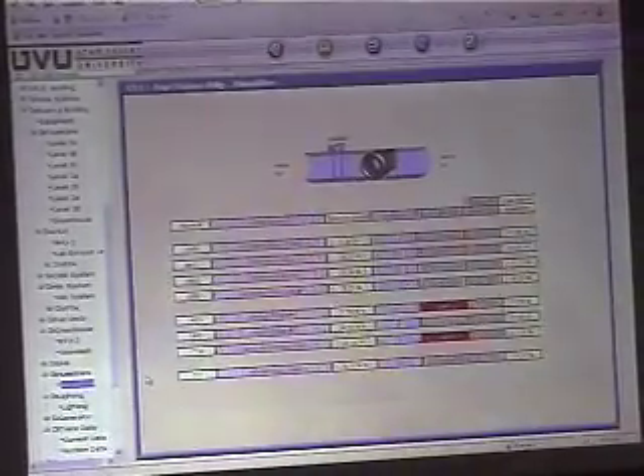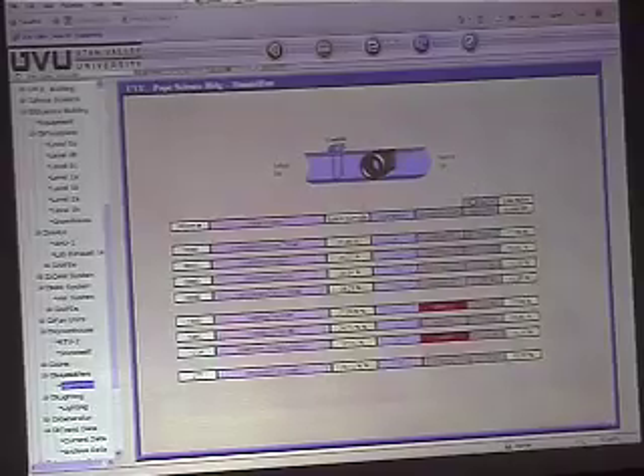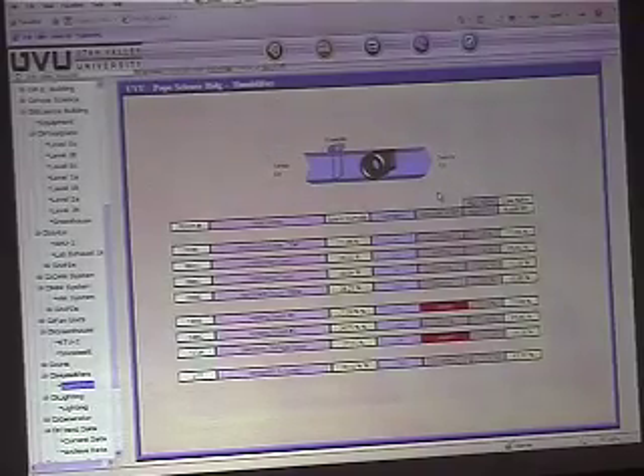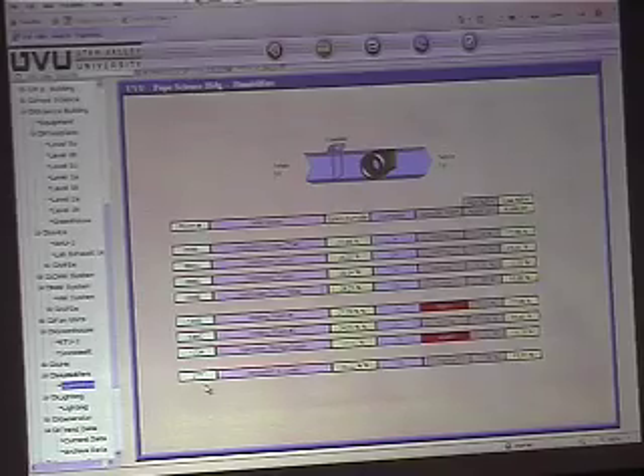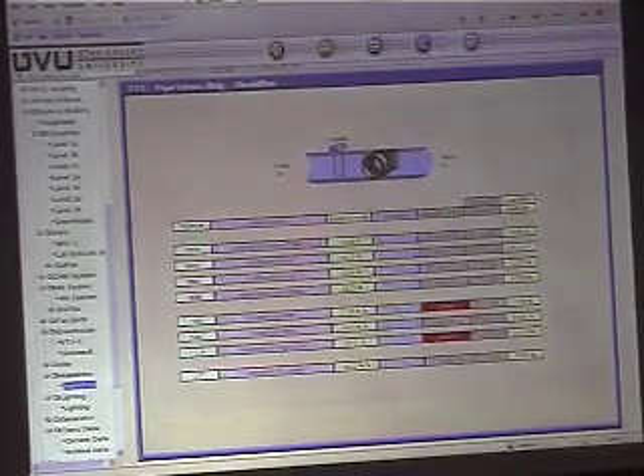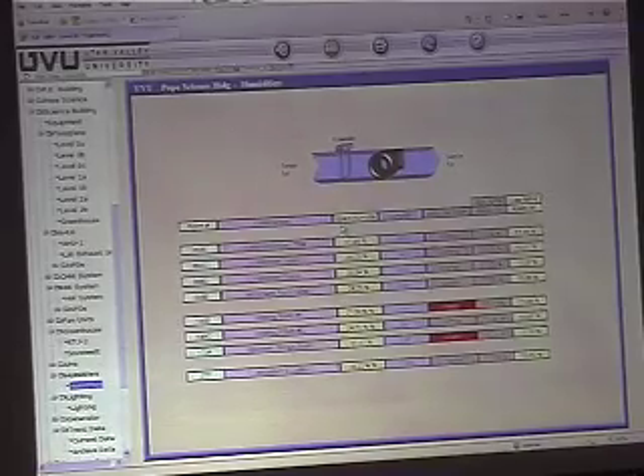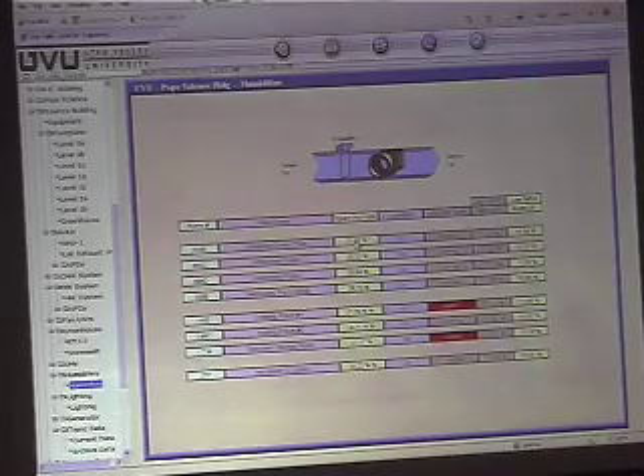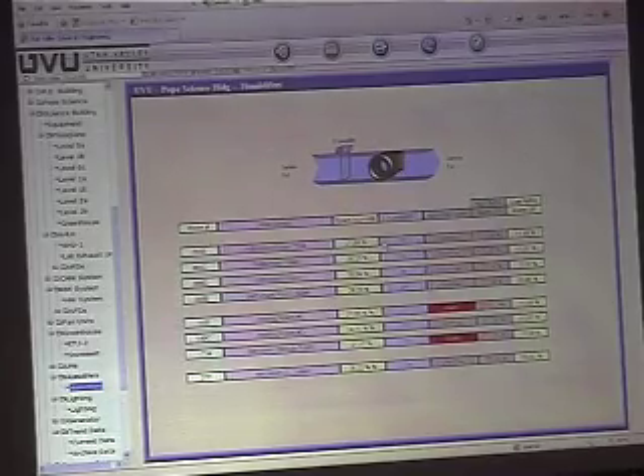There's some rooms that have humidifiers in them. So we built a matrix here to show all of the humidifiers. This is the room number that they're in. We monitor the humidity and we send a value represented by a 4 to 20 milliamp signal from our controller to the humidifier, and then we enable the humidifier. The humidifier basically pretty much runs standalone, so it's got its own built-in set point. And we can go to one of them.